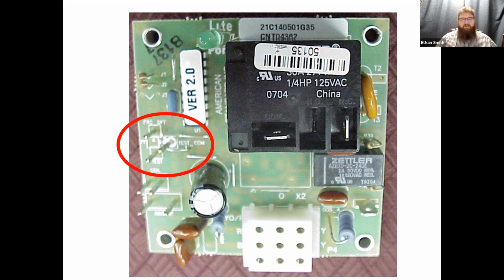Okay. Most defrost boards have a minimum defrost time of 1 minute and a maximum defrost time of 15 minutes. If you find that thing goes into forced defrost and then runs for 15 minutes, you may have a sensor that's not reading properly, or a central control board that's not reading the sensor inputs. So make sure you're testing that. And then of course we've got our termination where we can force the termination of a defrost cycle ourselves.